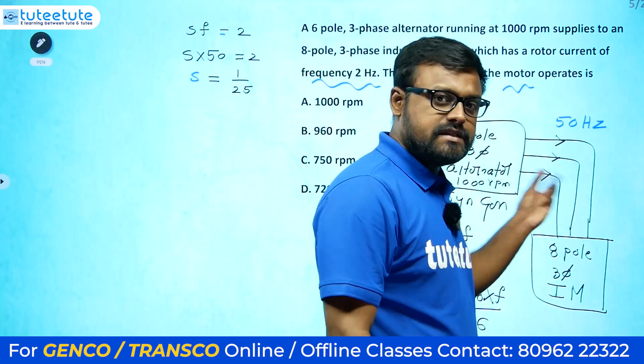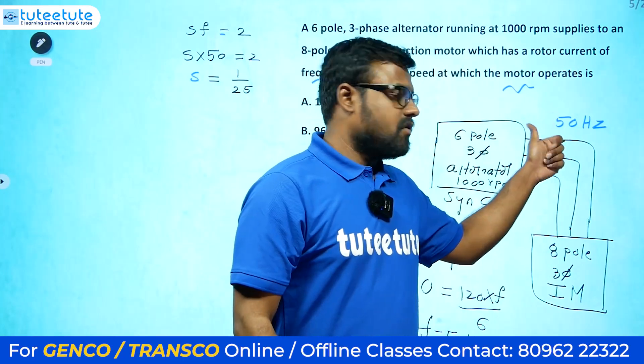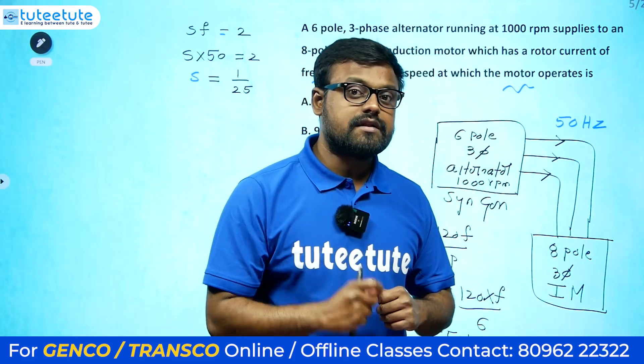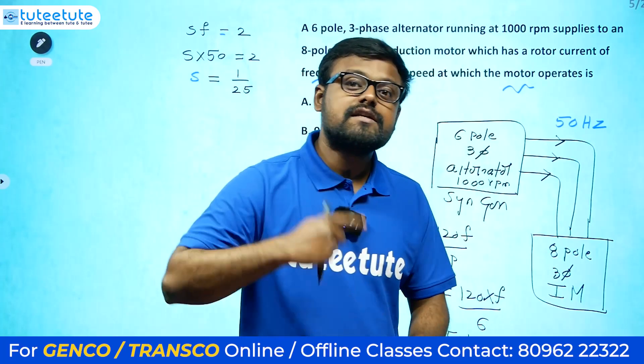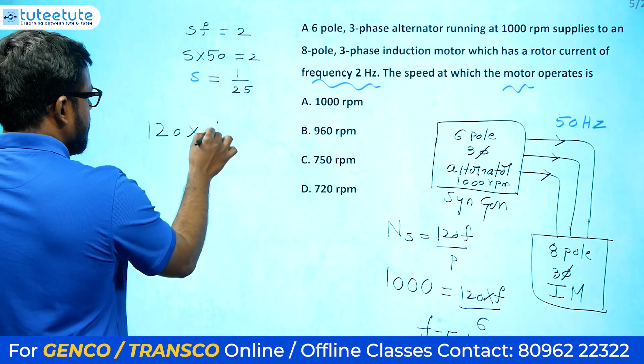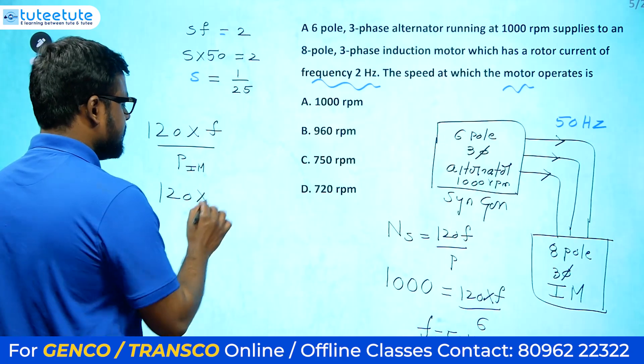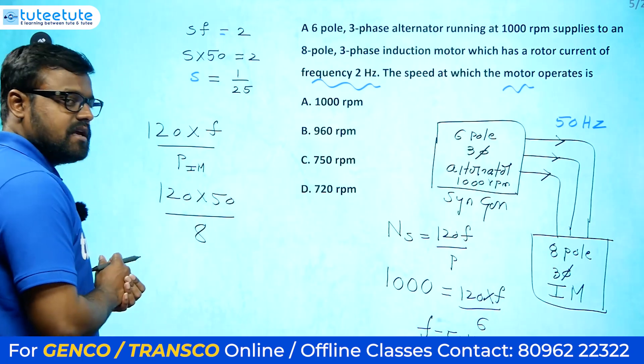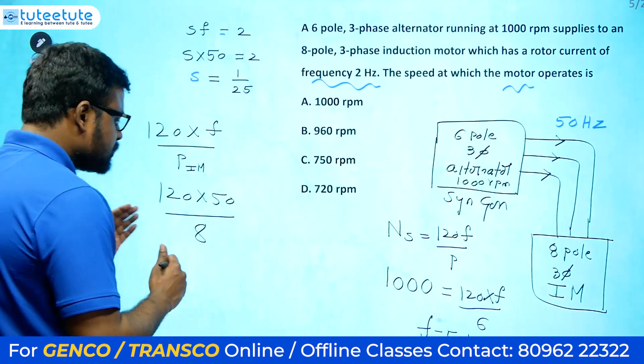When we give the 50 Hz supply to the stator of the induction motor, three-phase balanced currents flow in the three-phase winding, generating a rotating magnetic field. This rotating magnetic field rotates at synchronous speed, which is Ns = 120F / P = 120 × 50 / 8, where 8 is the number of poles of the induction motor.